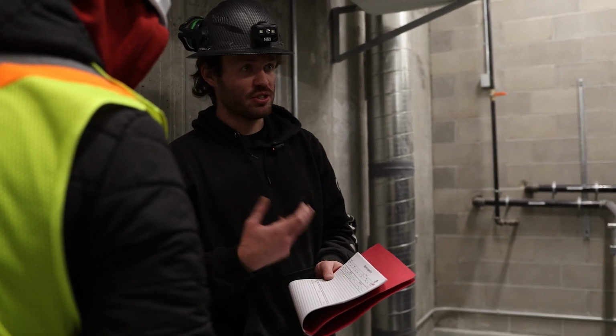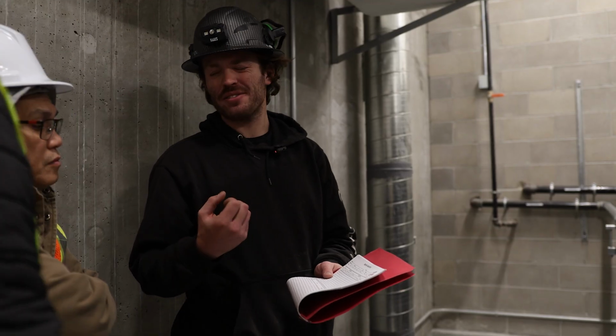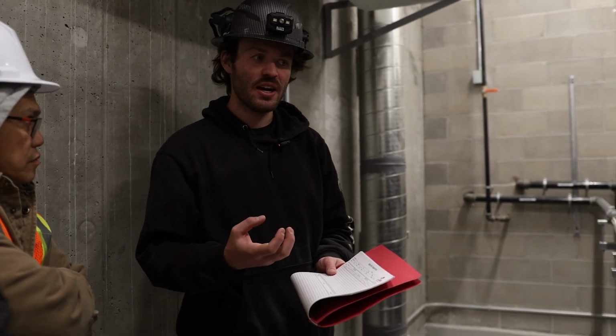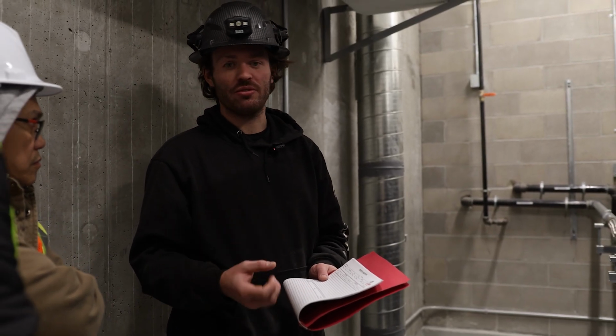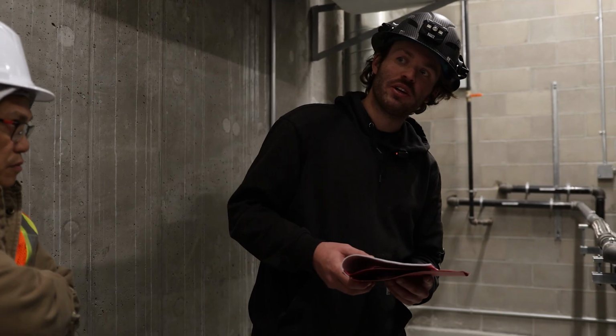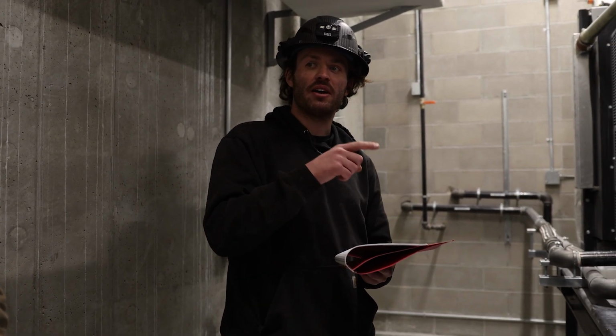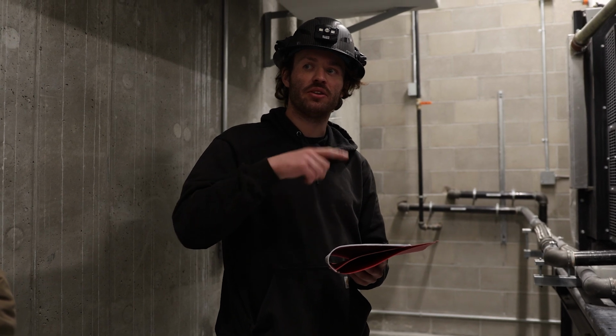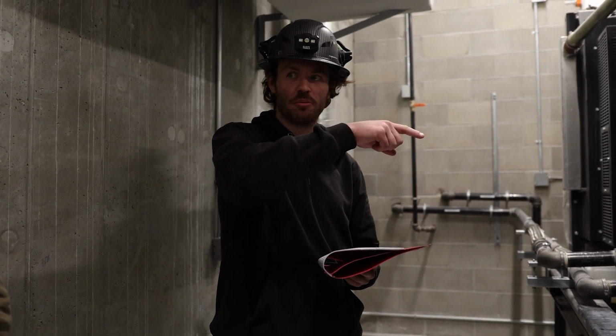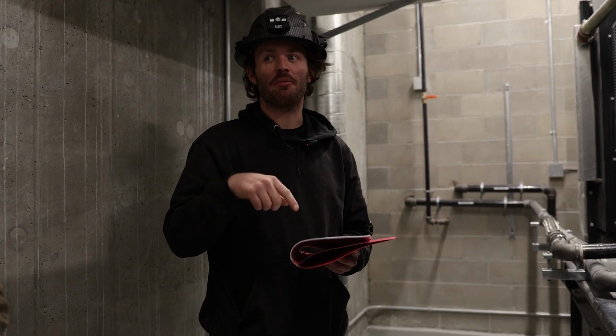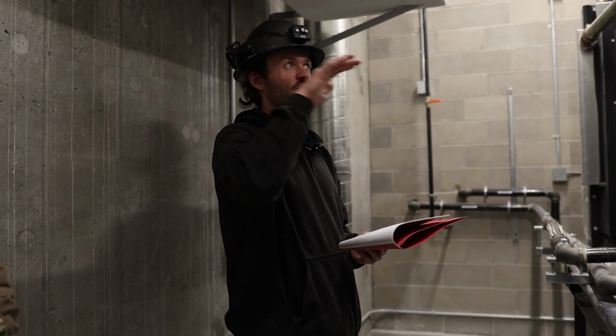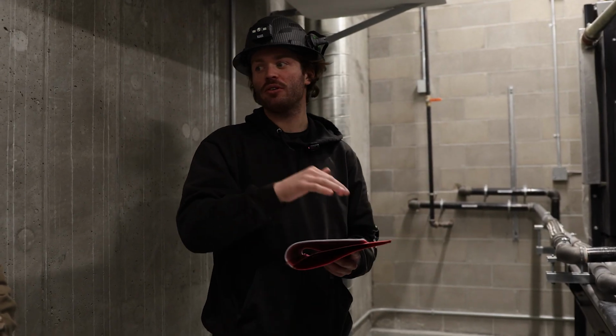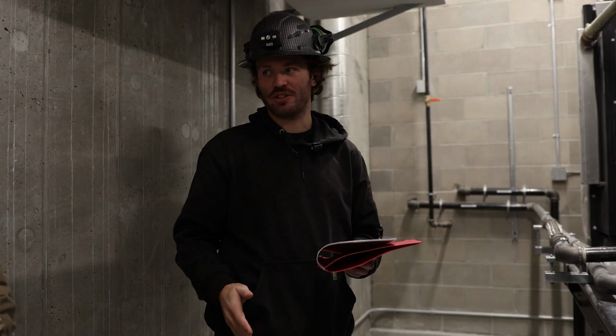Battery charger, make sure our charger is on. It's kind of hard to see on this guy, but if the battery charger were to fail, it's going to throw an alarm. Question for you, Vinny. Did it ever get changed over the emergency panel so if power is dead to the building, the generator is powering our shore panel? Because what would happen before is when the power would go out, this guy would get a battery charger fault because it's not powering its own battery charger.